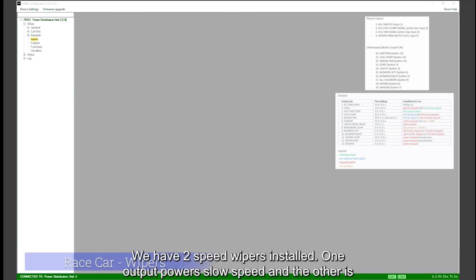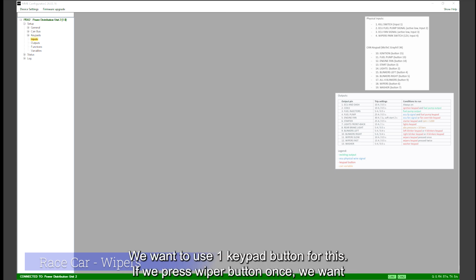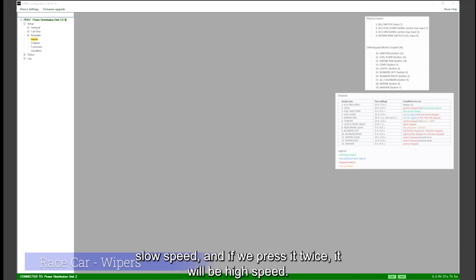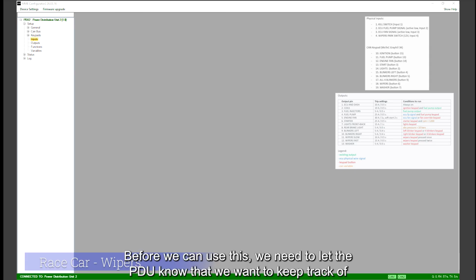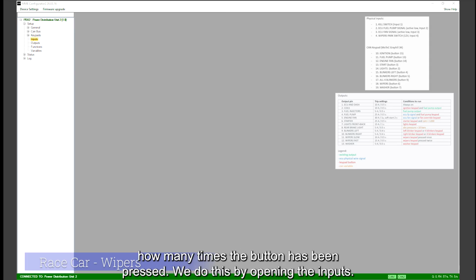We have 2 speed wipers installed. One output powers slow speed and the other is high speed. We want to use one keypad button for this. If we press wiper button once, we want slow speed, and if we press it twice, it will be high speed. If we press it the third time, wipers should turn off. Before we can use this, we need to let the PDU know that we want to keep track of how many times the button has been pressed.